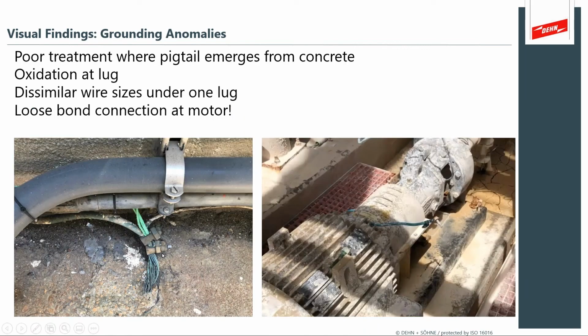Multiple wire sizes over one pigtail that emerges directly from concrete without connections, without protection over that conductor. Bonding connections that are hanging loose. So now you've got the potential that earthing faults are not protected. When you touch this motor housing, there could be an earthing fault, and there could be earth currents flowing that pose a safety hazard.